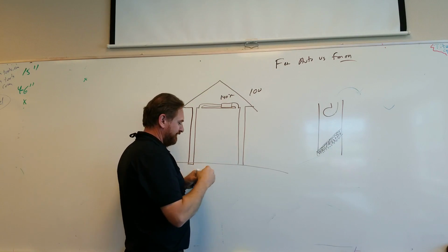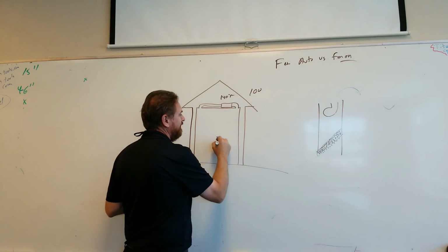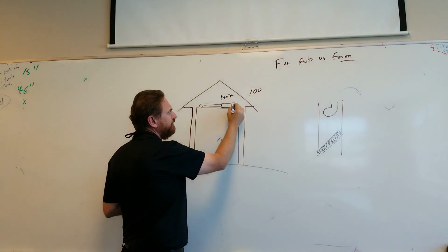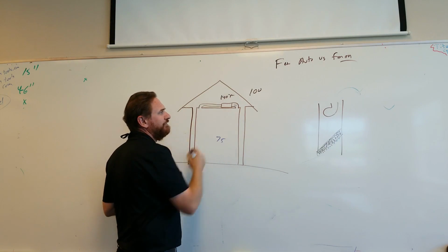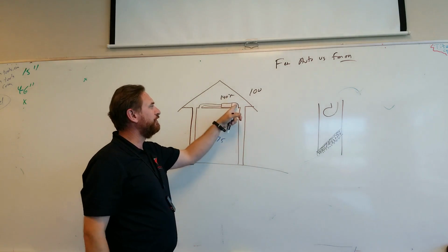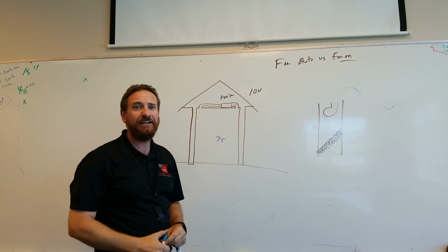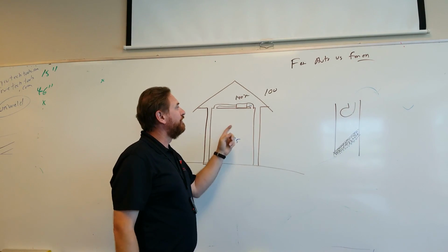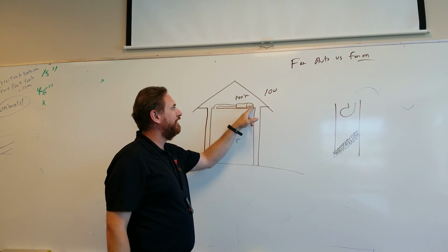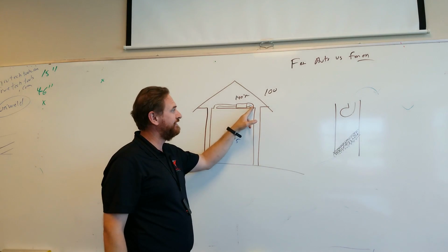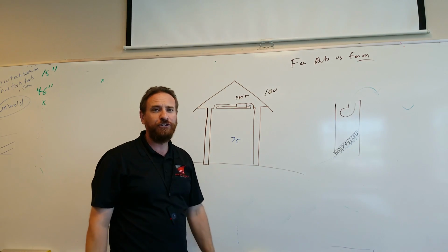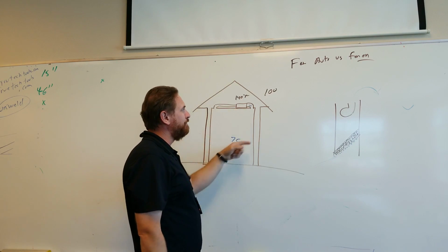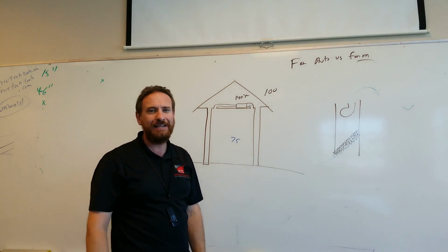Then the air in your house, let's say you have your temperature air at 75 degrees. So the return air that's going into the unit, 75 degrees, it's 140 degree air that's going in and heating up that air, just being in the attic alone. So as we run that fan, it's only 2 inches of insulation separating that 75 degree air from this 140 degree air. So the more air I move through that unit, the more heat I'm picking up.